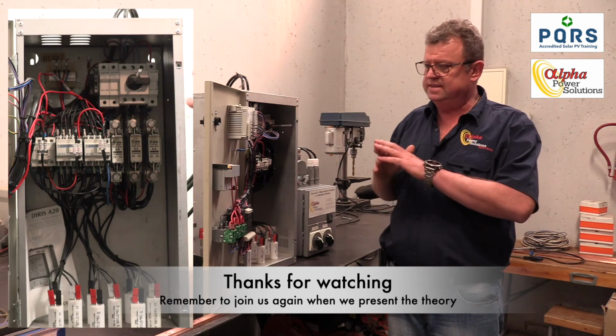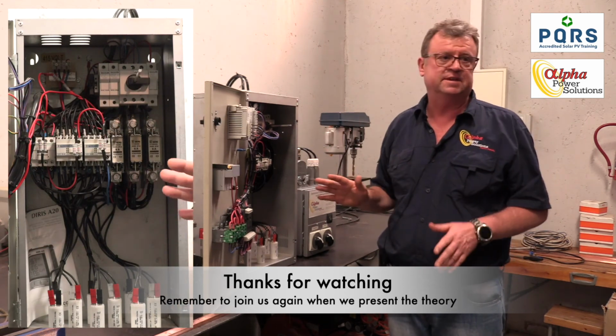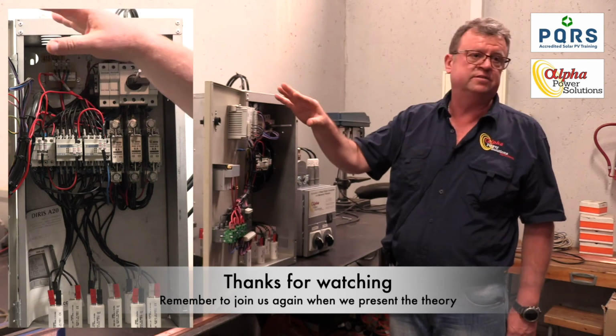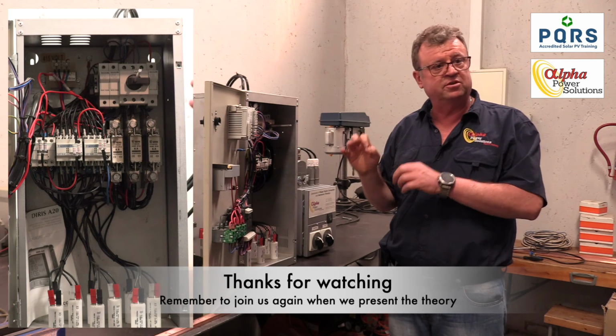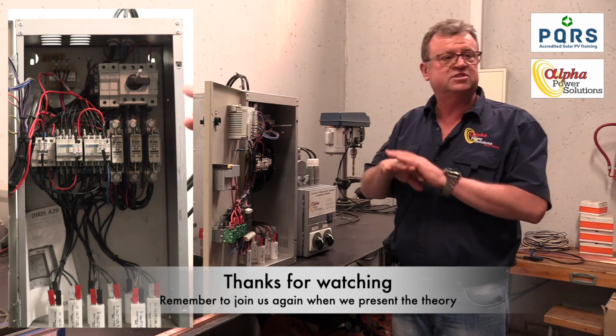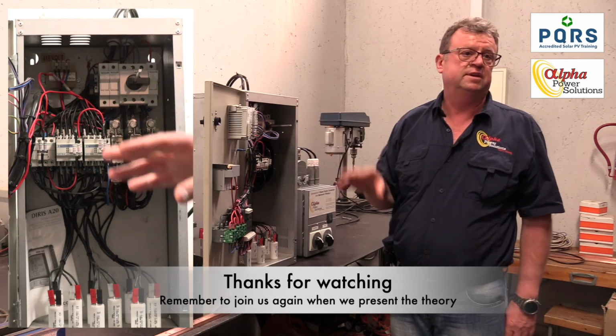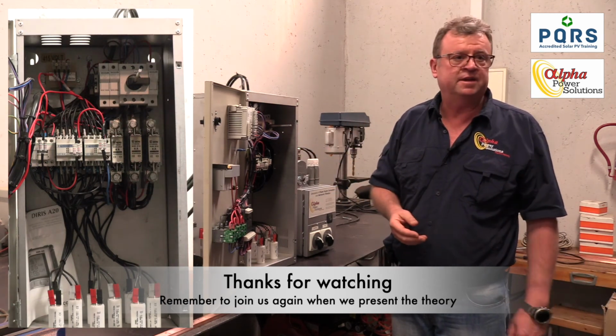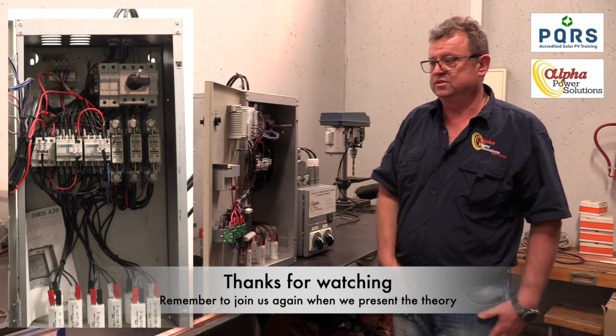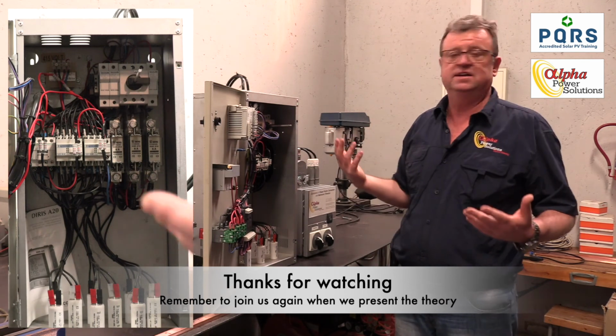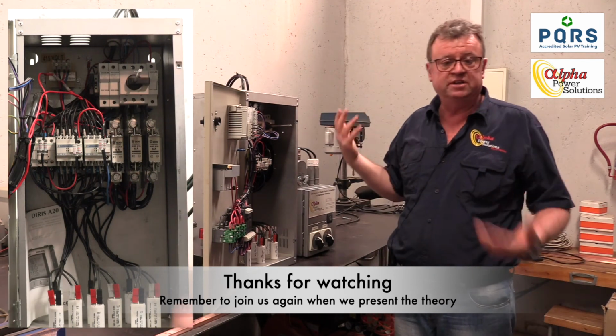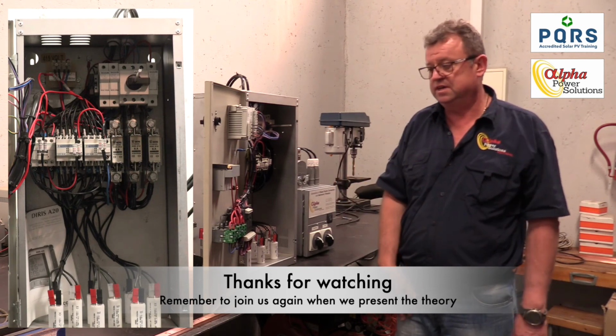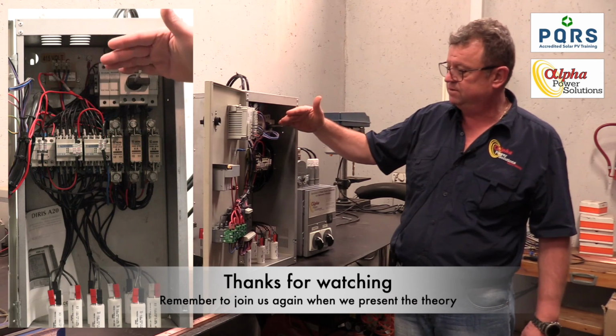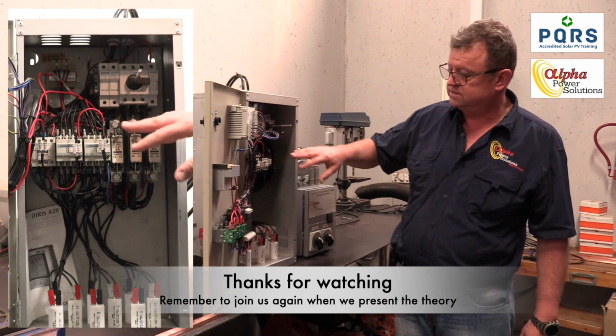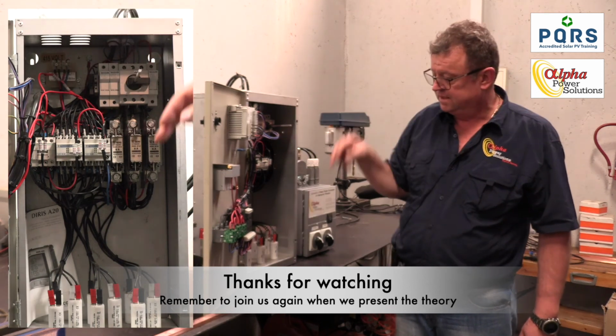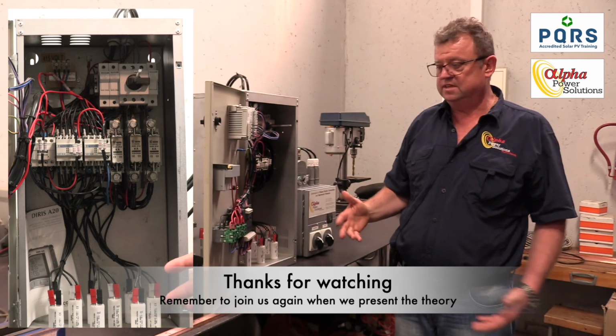Once it's installed, it is completely automatic. There's never a need to change any of the parameters in the controller. They were programmed, well, assuming they were programmed correctly, and they will stay there forever. No one needs to go and do any reprogramming or any of that stuff. So it's a self-managing device. If the power trips, it will just shut down and sit there and wait. It's an extremely simple device. You basically have incoming power, some protection, some contactors that are managed by the brain that then energize capacitors. So that's all there is to it.